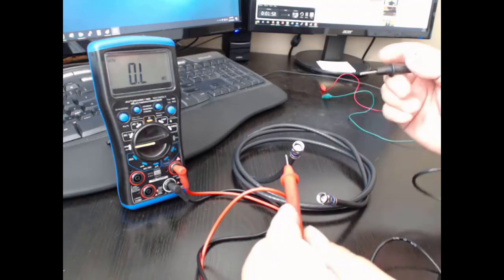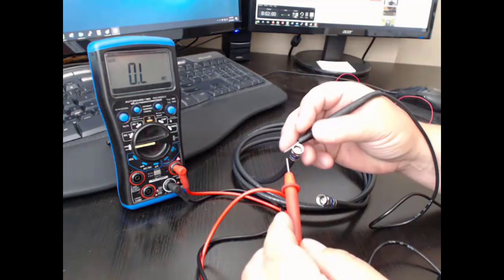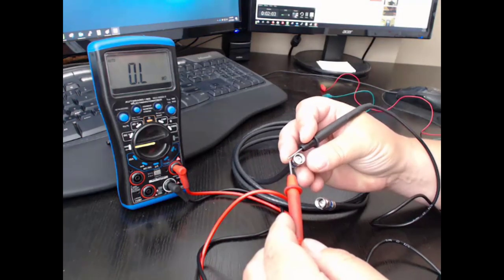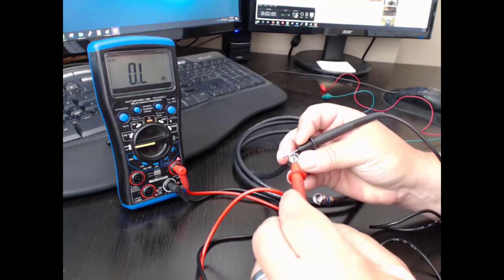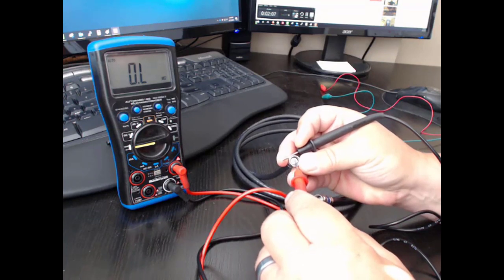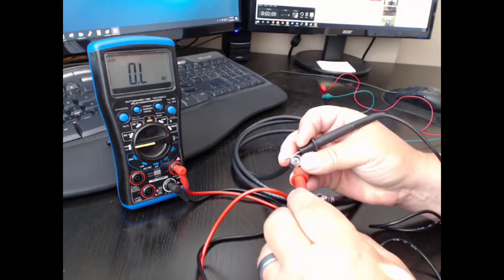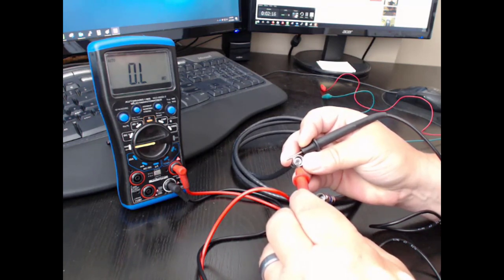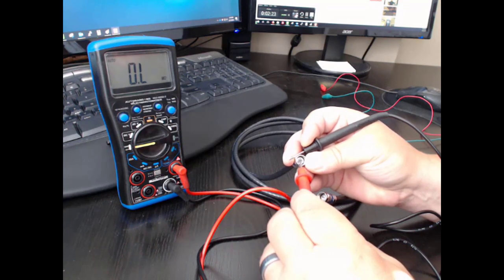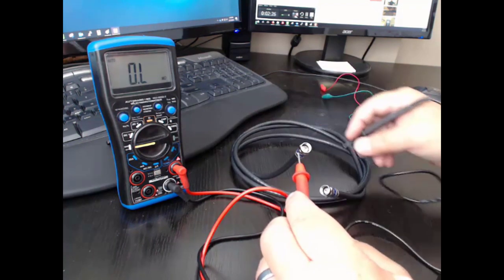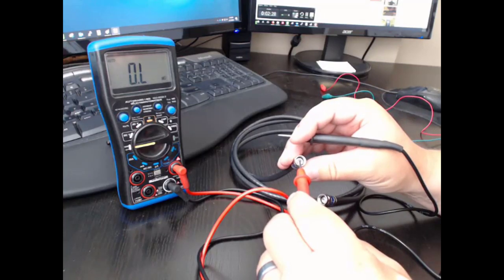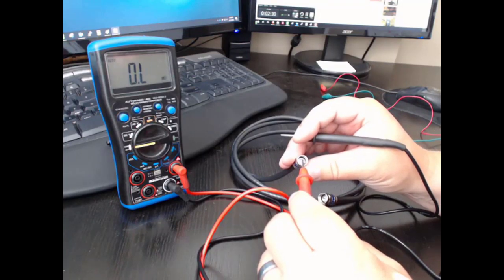To check this, put one probe on the connector nut and one probe on the stinger, being careful not to touch the sides. You can see I'm showing OL, or infinite impedance, basically acting like an open circuit, which is what we want. We don't want any continuity or path from the shield cable on the outside to the internal stinger. So that checks out okay.